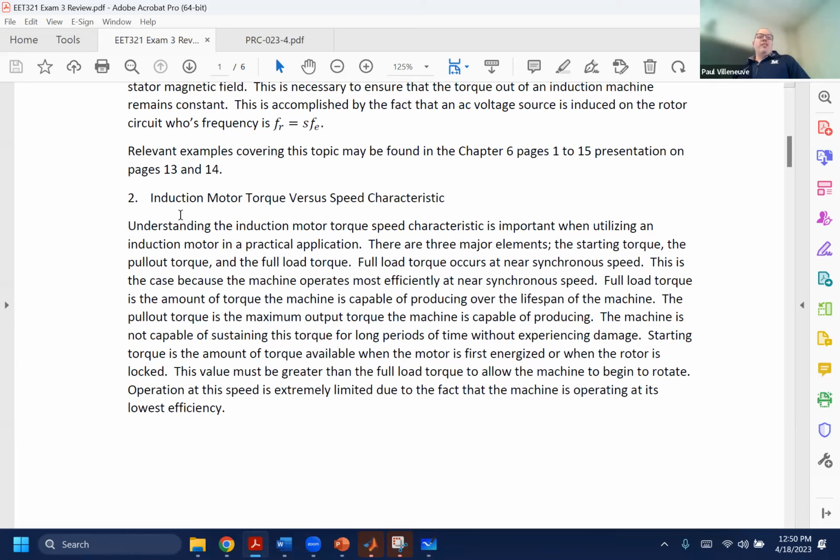You don't often see this, and again, this is very limited because I haven't specified a lot of motors where I've had to get into this level of detail, because again, who specifies the motors? Sounds crazy, but it's usually the mechanical engineers that specify the motors, because they're the ones who know what the load is going to be. So they know it needs to be 100 horsepower at 3200 RPM or whatever. They do all the calculations to figure that out.